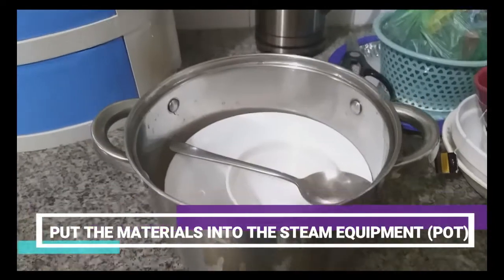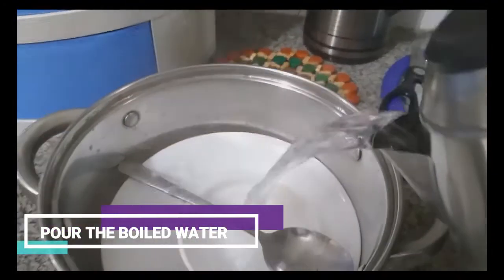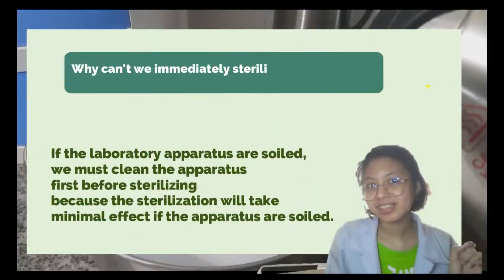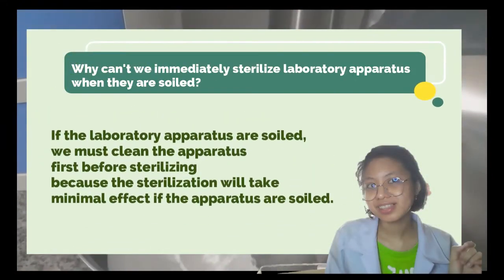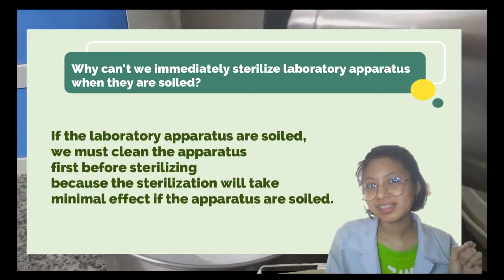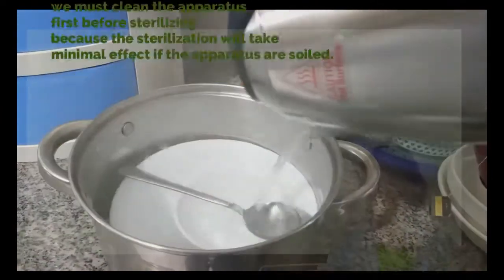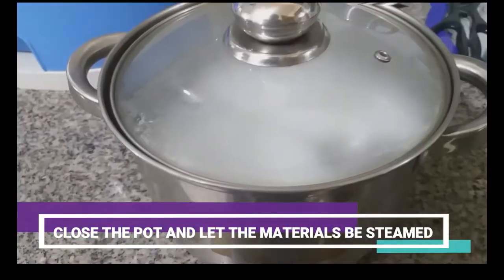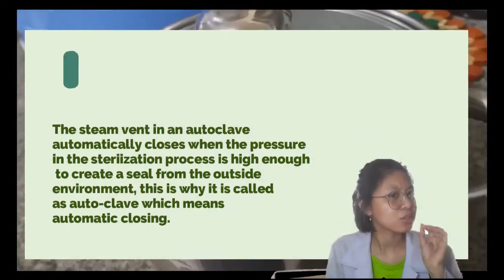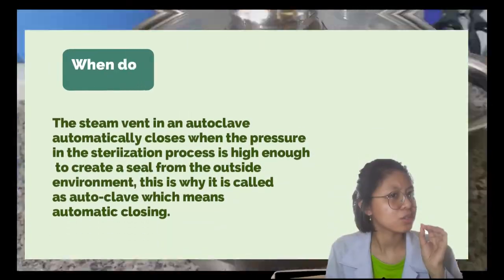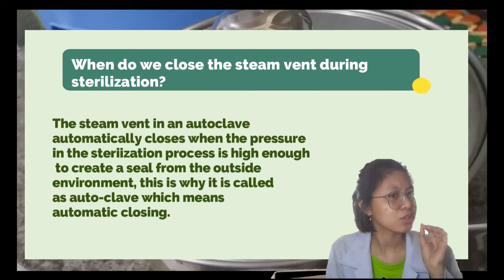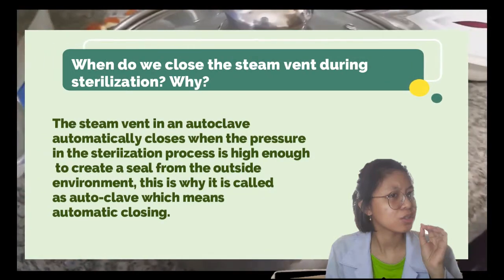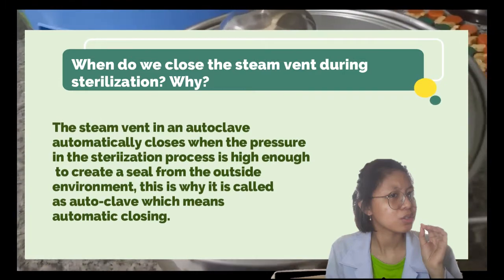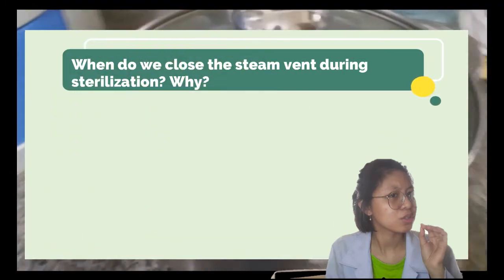In a laboratory setup, an autoclave is the proper equipment for sterilization. If the laboratory apparatus are soiled, we must clean the apparatus first before sterilizing because the sterilization will take minimal effect if the apparatus are soiled. The steam vent in an autoclave automatically closes when the pressure in the sterilization process is high enough to create a seal from the outside environment. This is why it is called an autoclave, which means automatic closing.